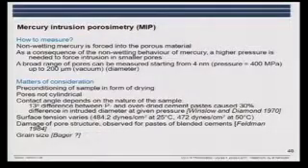So, how do we measure? We press mercury into the porous material, which has been dried beforehand, and increasing pressure causes the mercury to go into smaller and smaller pores. We have to precondition the sample, we have to dry it beforehand, so that's one of the matters of consideration.